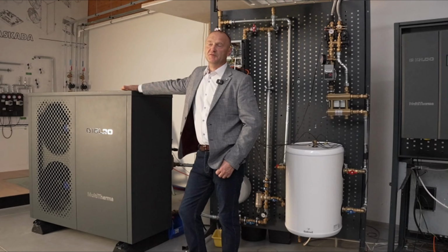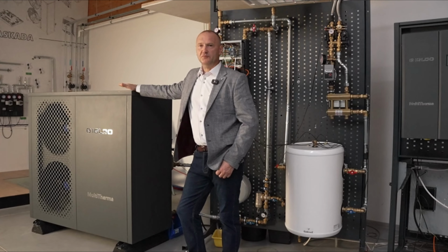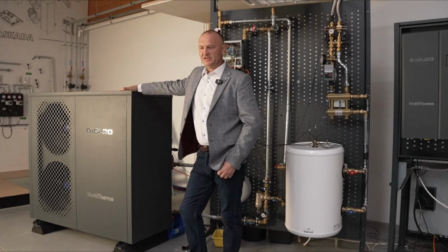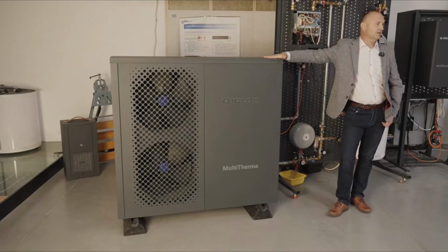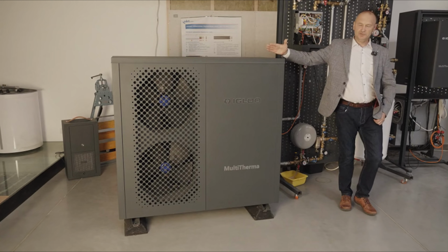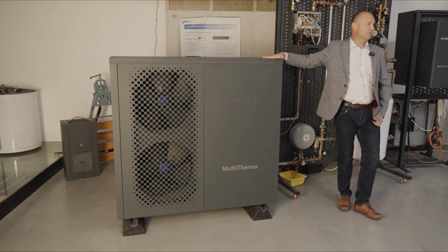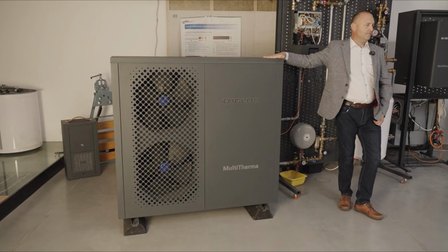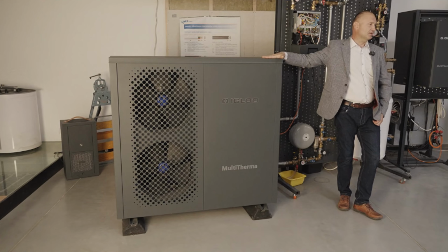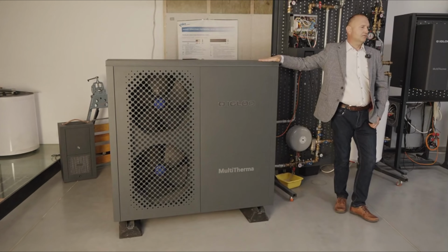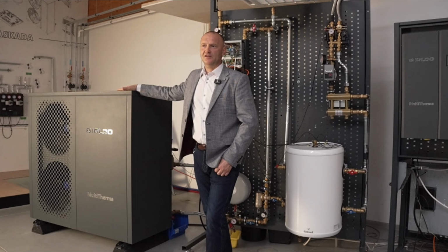So if we were to simply imagine that we have a small house where a pump like this is operating and it's perfectly sufficient for heating that entire house throughout the whole year, and then next to it we were to build a second identical house, operated in precisely the same manner and connected to it. Instead of just one MultiTherma 12 unit, as in the first instance, we connected two MultiTherma 12 units, which would effectively be like a pump twice as large, a cascade of two pumps. This might sound paradoxical, but the house that will have two devices will actually consume less energy than the one that has only one device.